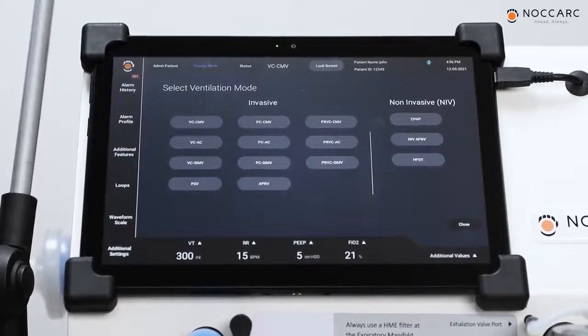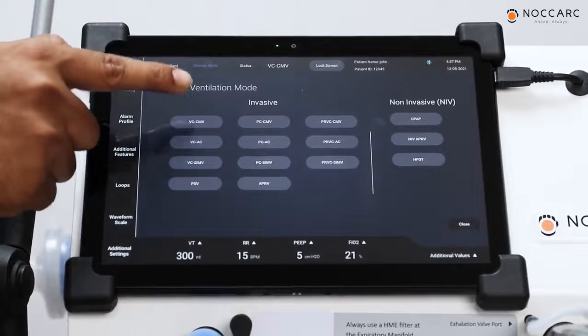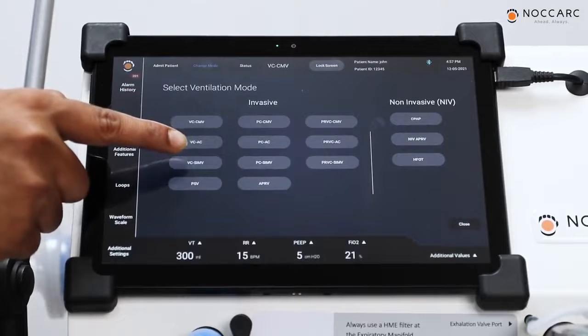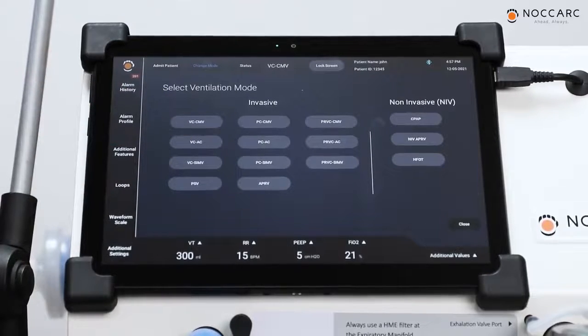Here you can see the company has provided invasive and non-invasive ventilation modes. For invasive, a total of 11 modes are provided, and for non-invasive, 3 modes are provided, including integrated HFOT, that is high flow oxygen therapy. If you look at invasive modes, continuous mandatory ventilation, assist control, and synchronous intermittent mandatory ventilation can be operated as volume control, pressure control, and pressure regulated volume control. For non-invasive, the company has provided CPAP, NIV APRV, and HFOT.